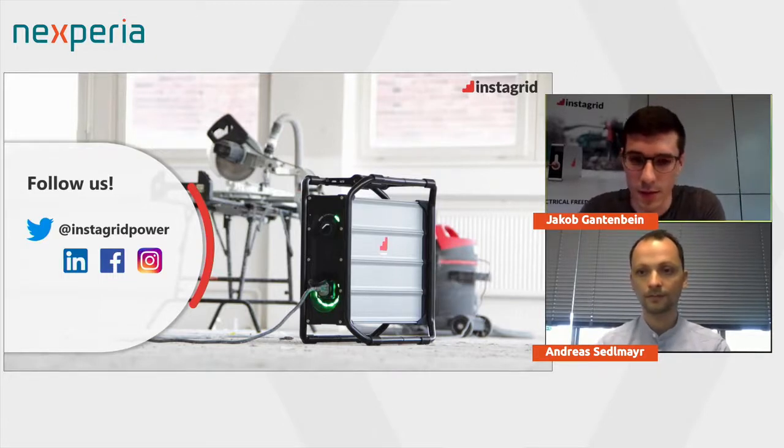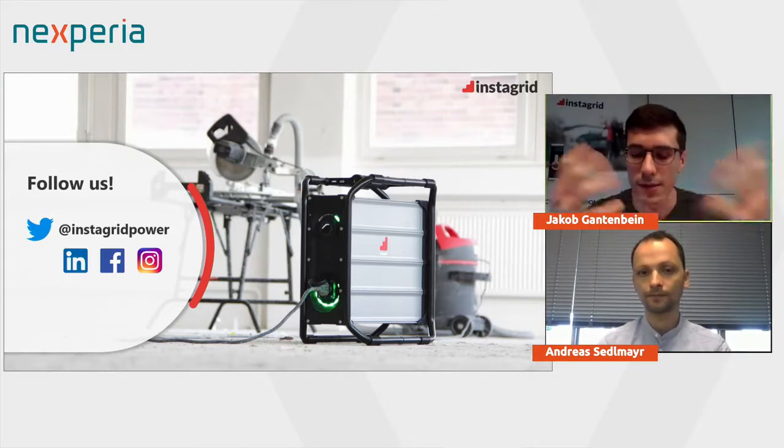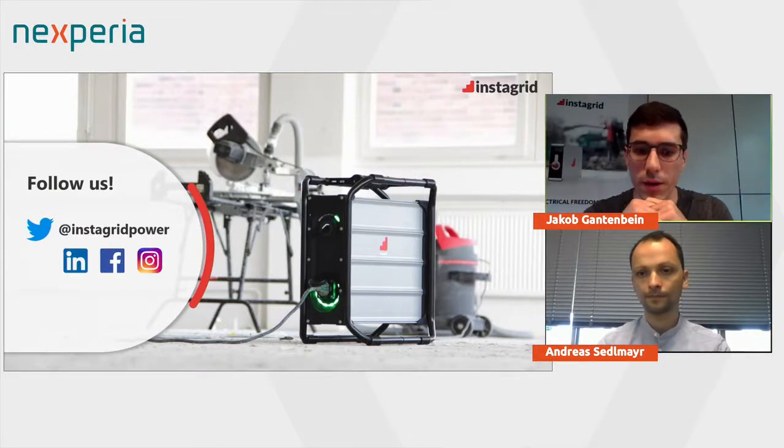The heat is just measured, and then there's not really a lot of heat management necessary. Only when charging, there's a limit, so it doesn't get overheated, and obviously there's an emergency shutdown if the unit gets too hot. Apart from that, the cell management is active, so it's always during charging and during discharging. The amount of current each of these modules or each of these levels gets is adjusted depending on how high it is charged. Maybe if I can add on that, it's the efficiency of the system.